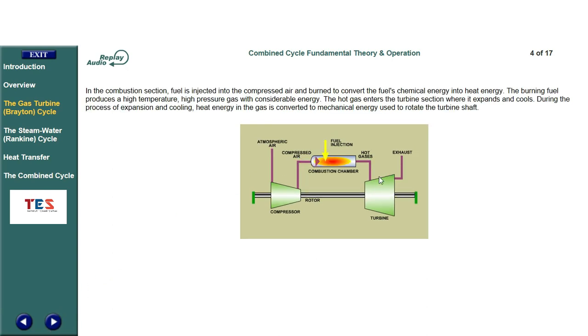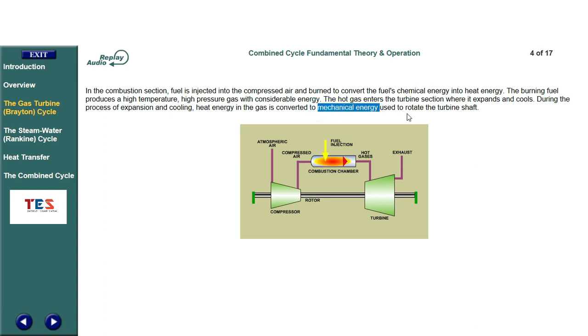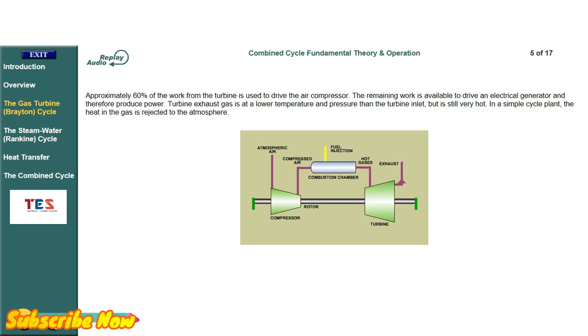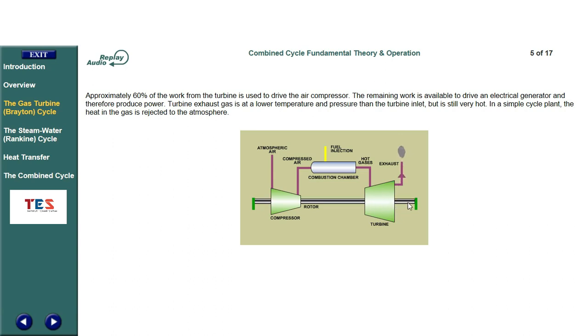In the combustion section, fuel is injected into the compressed air and burned to convert the fuel's chemical energy into heat energy. The burning fuel produces a high temperature, high pressure gas with considerable energy. The hot gas enters the turbine section where it expands and cools. During the process of expansion and cooling, heat energy in the gas is converted to mechanical energy used to rotate the turbine shaft. Approximately 60% of the work from the turbine is used to drive the air compressor. The remaining work is available to drive an electrical generator and therefore produce power. Turbine exhaust gas is at a lower temperature and pressure than the turbine inlet, but is still very hot. In a simple cycle plant, the heat in the gas is rejected to the atmosphere.